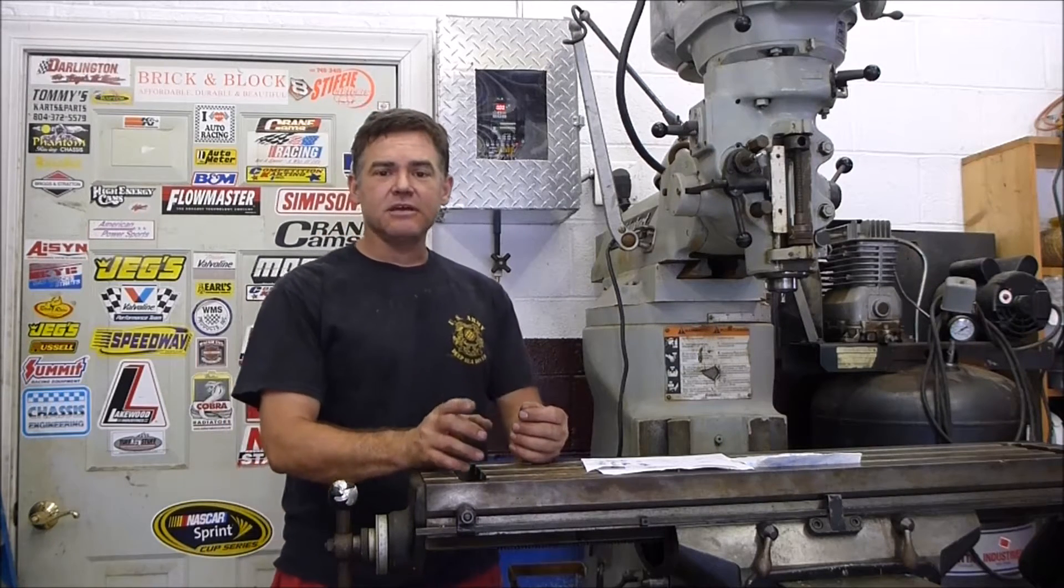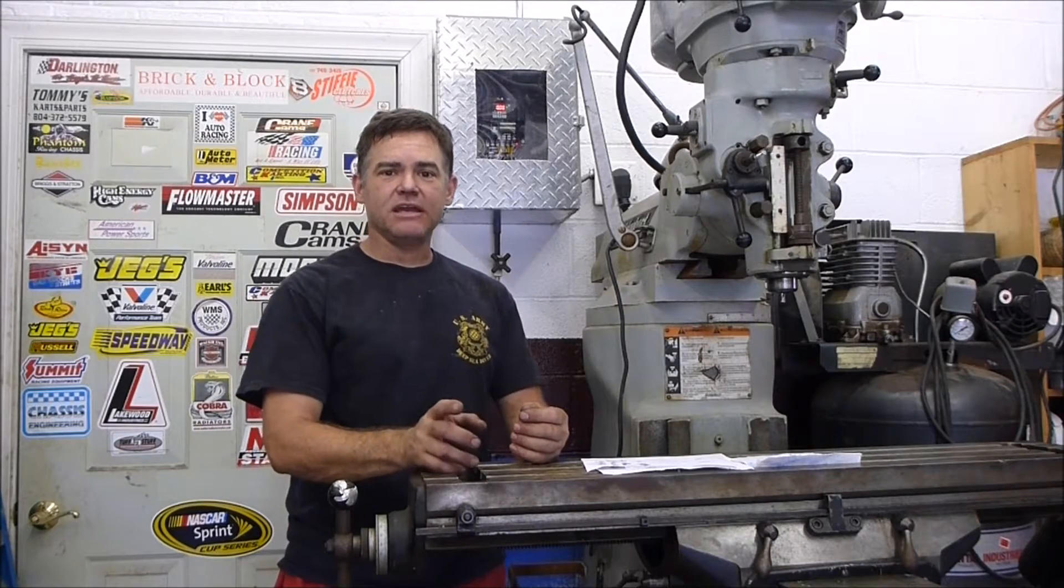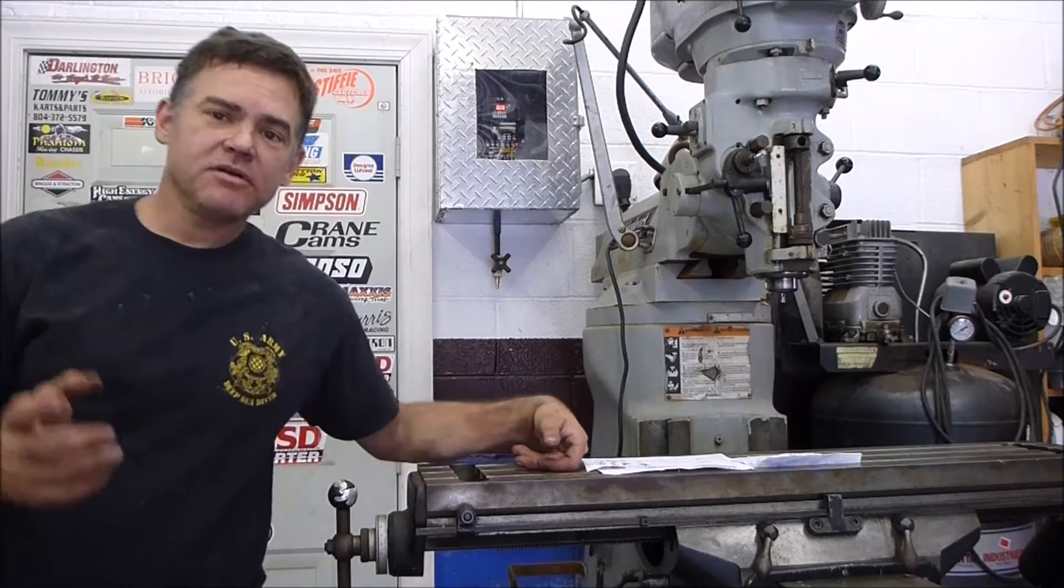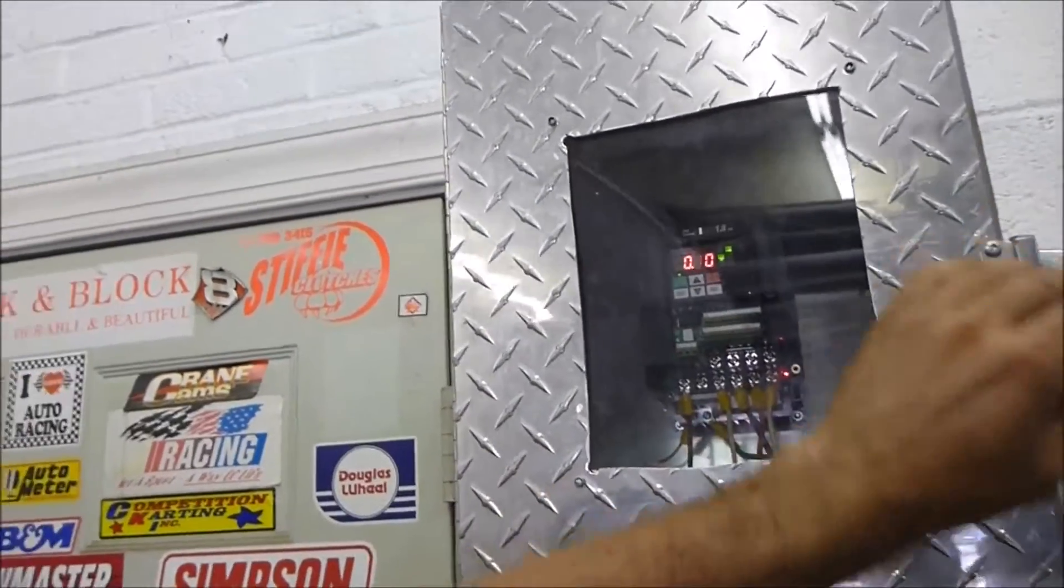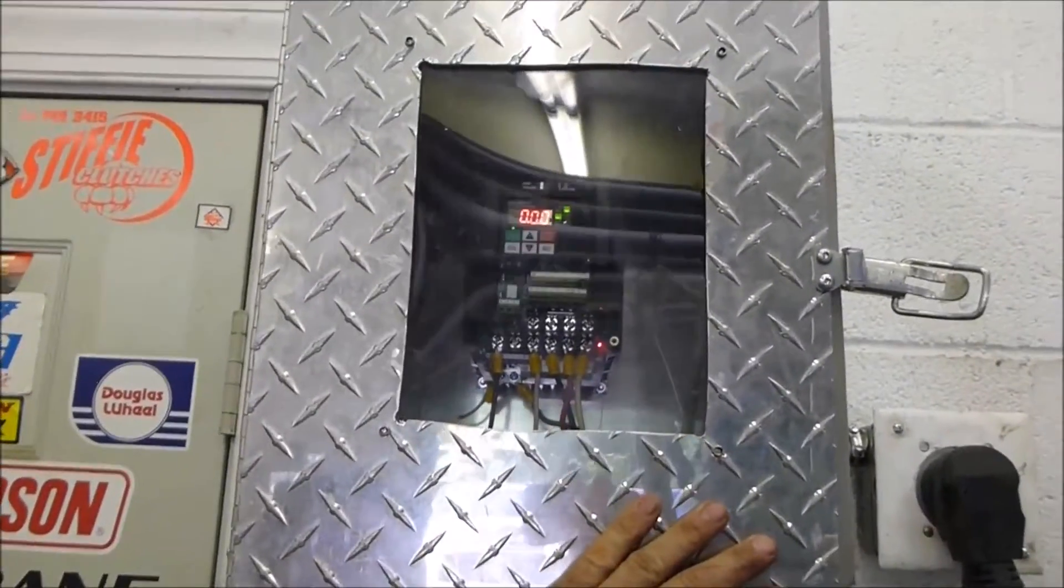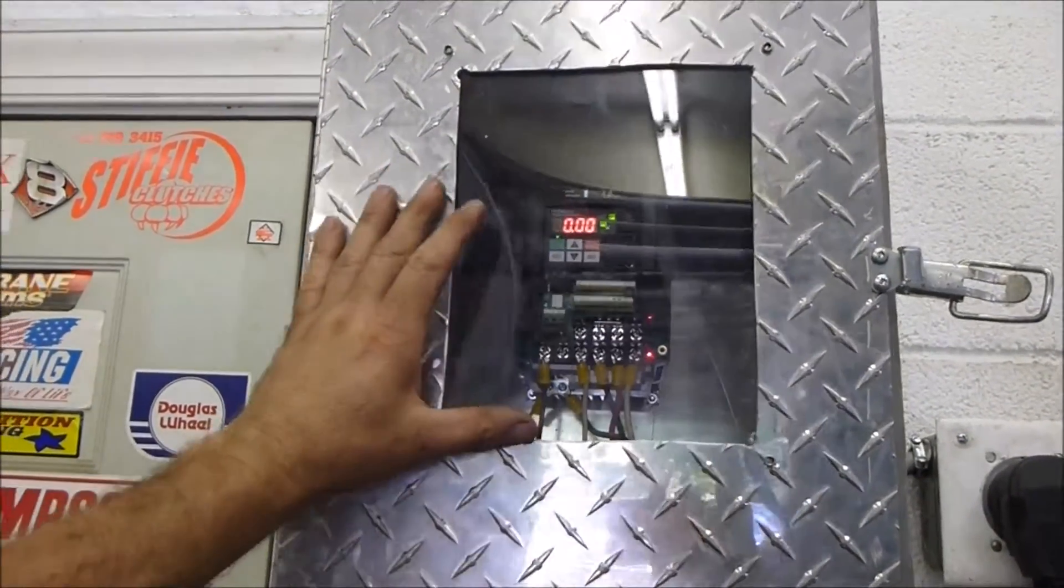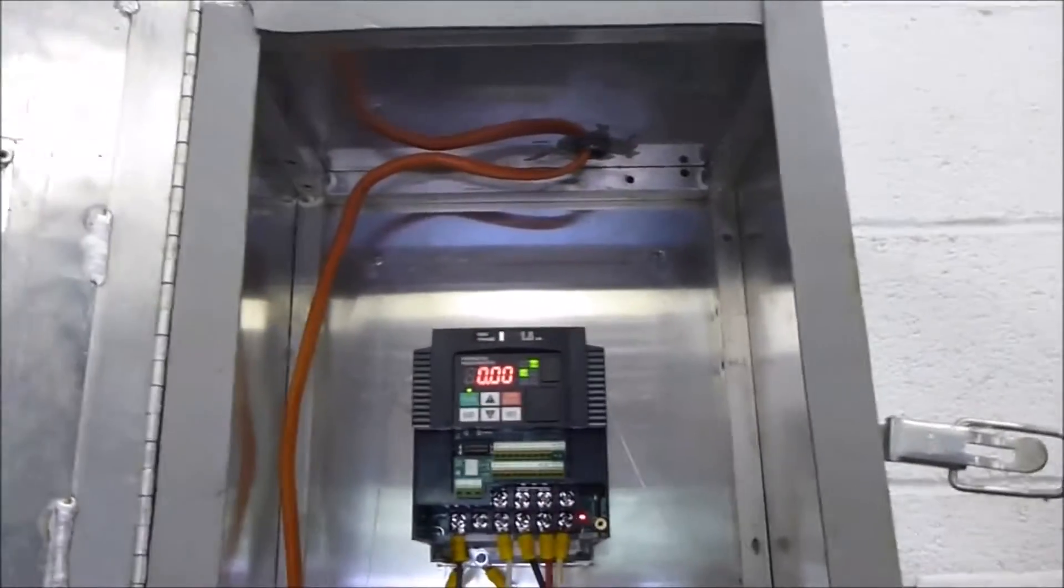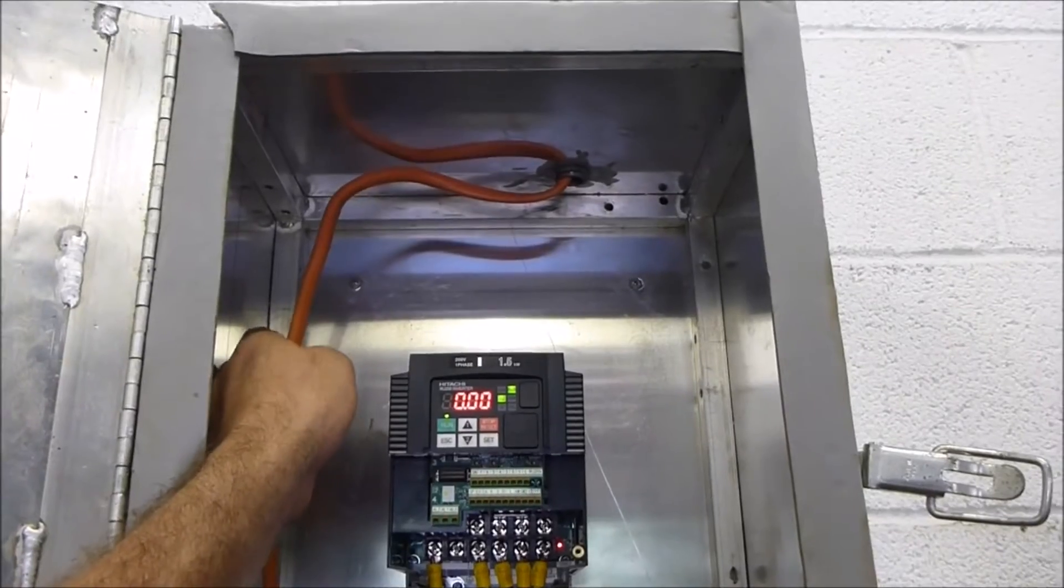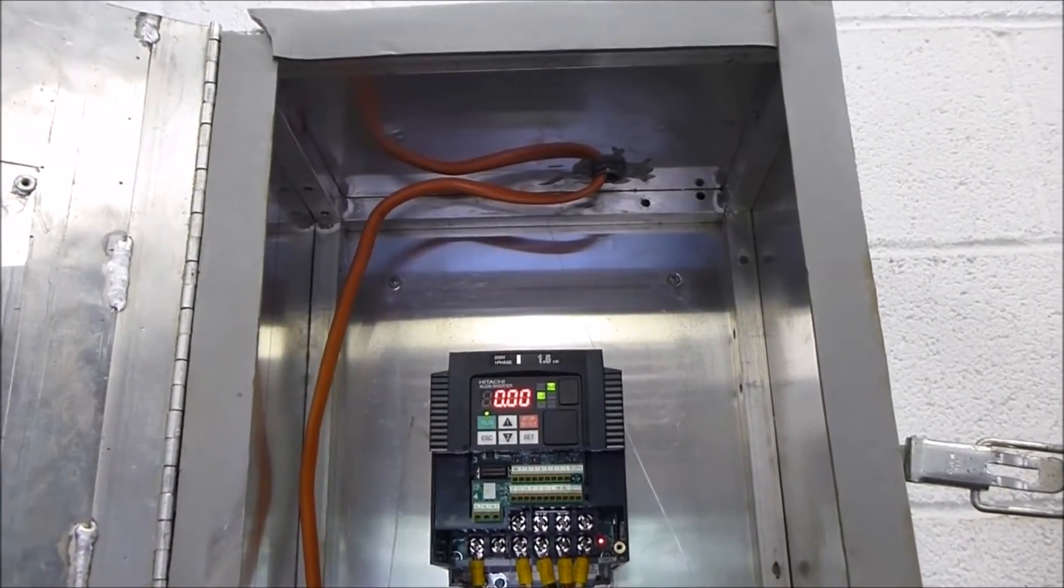In order to connect this together, I went ahead and ran a hard line from my circuit panel. I have a dedicated 30 amp breaker, which I then used for my VFD. I created an enclosure with a see-through screen so that I can look at it and protect it. The line from my dedicated breaker comes through the EMT, ran it over to the VFD.